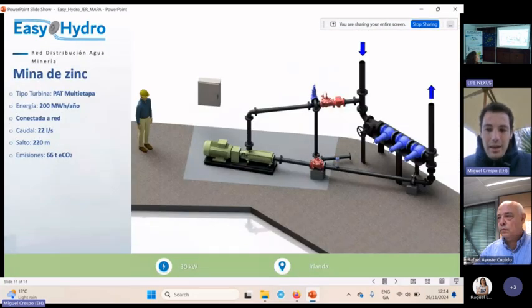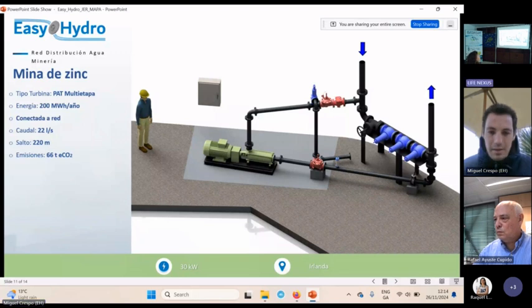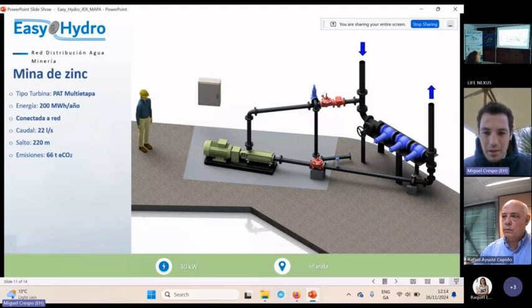This is in an underground mine. In some of the presentations before, I saw that the range of head for single stage centrifugal PATs could go up to 100 meters. This case, for instance, with this multi-stage PAT, we are taking advantage of a head anticipated by those three blue valves.